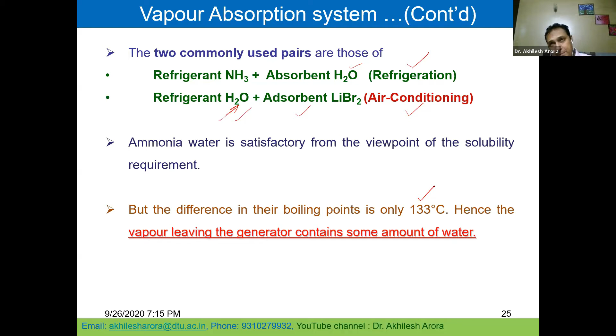So thus the ammonia water system is not suitable from the viewpoint of the boiling point requirement. From the solubility point of view, it is okay. Whereas if you talk about the water lithium bromide system, water is the refrigerant, lithium bromide is the absorbent, and the boiling point difference is 700 degrees Celsius. So it's much more than 200 degrees Celsius. Hence, the mixture of water lithium bromide is used only in air conditioning application.